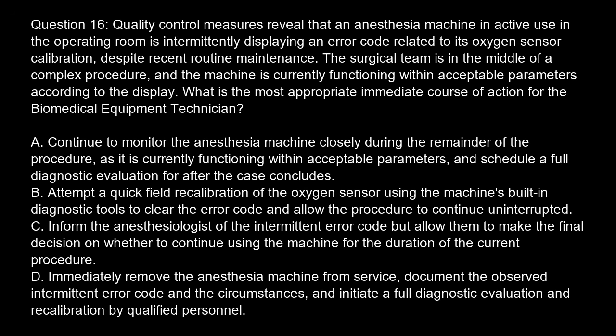Option B. Attempt a quick field recalibration of the oxygen sensor using the machine's built-in diagnostic tools to clear the error code and allow the procedure to continue uninterrupted. Option C. Inform the anesthesiologist of the intermittent error code, but allow them to make the final decision on whether to continue using the machine for the duration of the current procedure. Option D. Immediately remove the anesthesia machine from service, document the observed intermittent error code and the circumstances, and initiate a full diagnostic evaluation and recalibration by qualified personnel.